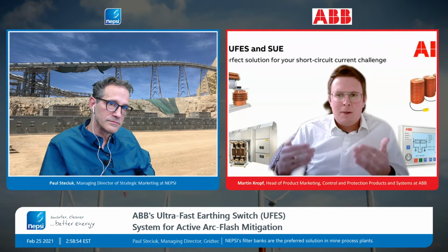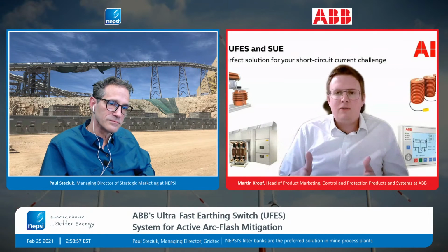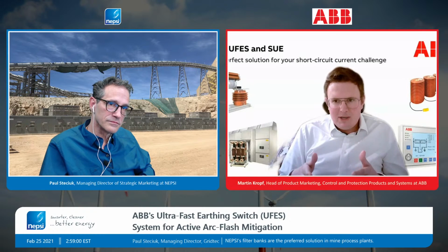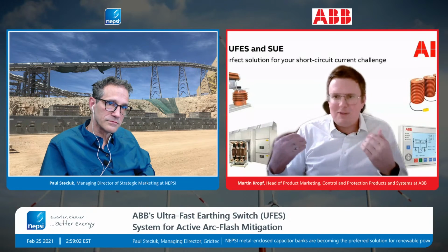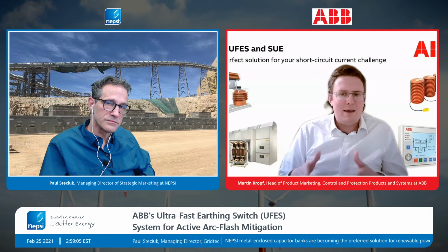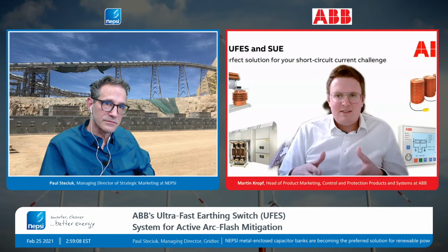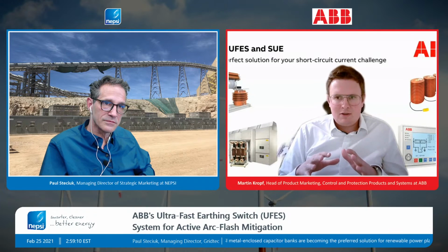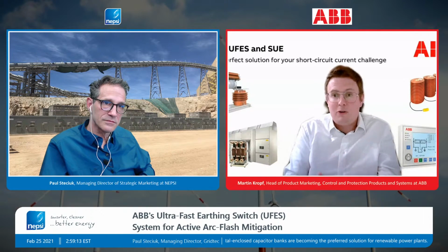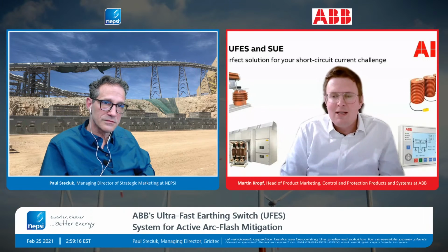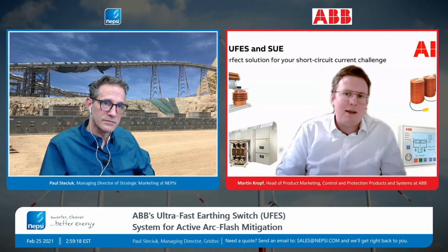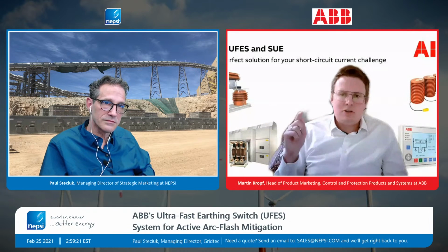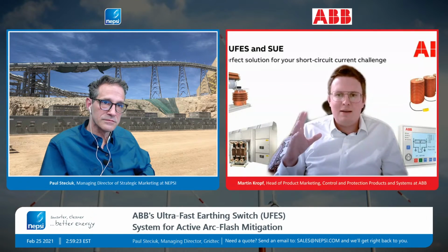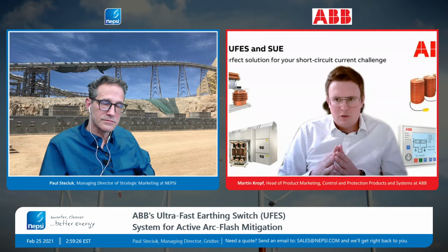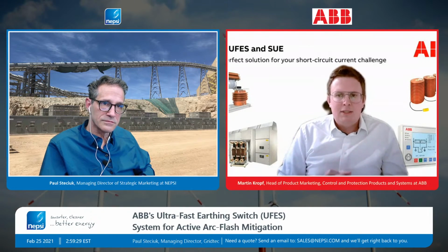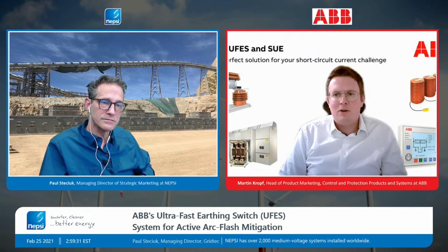So the idea is, you have a fault, you go to site. First, don't be in a hurry. Even though you have a very expensive production, you have to first see what really happened. So you're investigating, disconnecting in a concentrated way, maybe the faulty compartment, cleaning, checking what really happened. Then you change the 3 primary switching elements, it's plug and play, and you can just reset the electronics and it's ready again, because it's only ready if it has 3 fresh charges of microgas generators there, and then you're good to go.